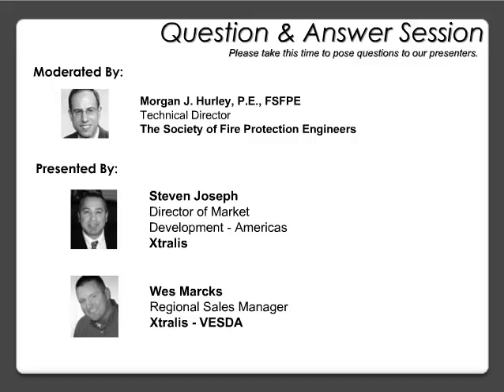So other types of material can be used, and sometimes that's desirable if, for some reason, they want a metallic tubing. The key thing, it's got to be airtight except for the sampling holes. It's got to be modeled in the design program, to model the airflow with the diameter that's being used. And it's got to be properly identified, per NFPA 72. So different manufacturers have stickers to identify the tubing as air sampling type tubing. But again, the most common type is the CPVC 3/4 inch Schedule 40. Excellent. Thank you for that.